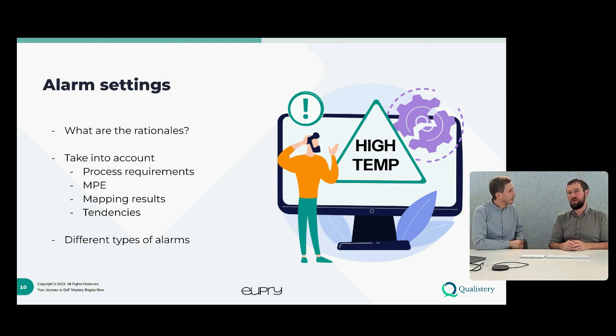And exactly, it's a really good point. What we often see as well is that if the requirements for your process are not set, how are you going to set alarm settings? And if you don't have your process requirements, how are you going to choose calibration MPEs and calibration points? So it all ties together. I think the foundation for a lot of this is setting the requirements correctly and clearly, which alleviates some of the decision making regarding how to set alarm settings and calibration points, because what do we refer to?